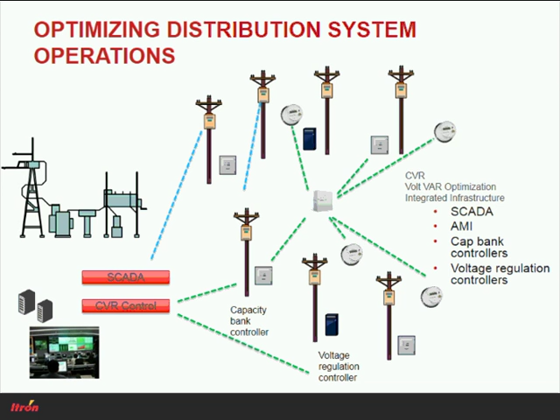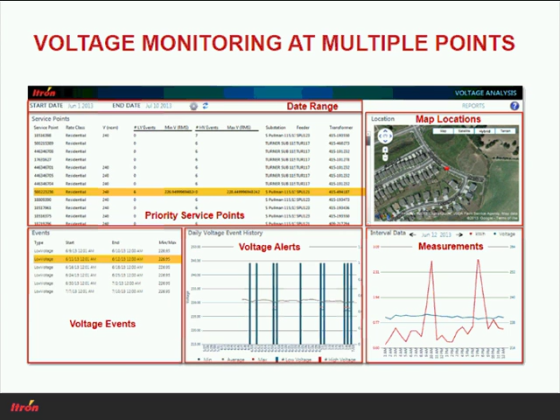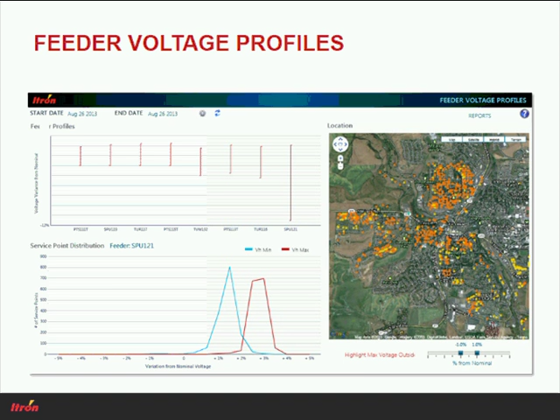So I want to quickly go through some things that are done right now by utilities. Voltage monitoring is pretty common, and nowadays you can monitor voltage at multiple points and get a lot of information about what's occurring anywhere within your distribution system with voltages, whether that's the condition relative to under or over voltage. You can look at time series and begin to look down into individual transformers to better understand the health of the voltage condition within the system. You can look at feeder voltage profiles and get a sense of what's happening with voltage over time at different branches and distribution feeders, so you begin to get a more holistic picture of what's going on with the distribution system.